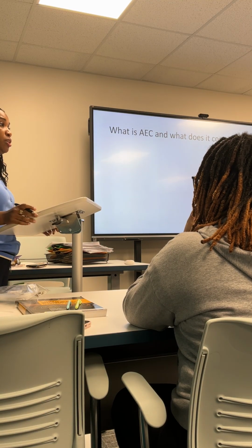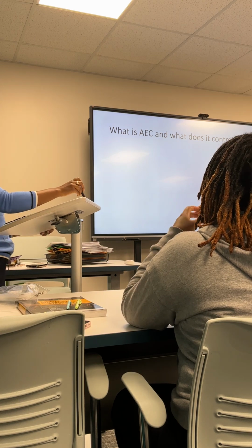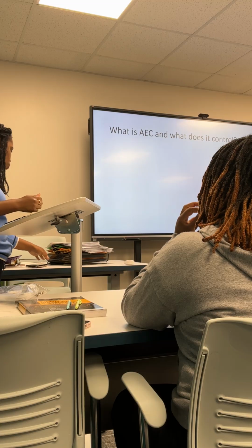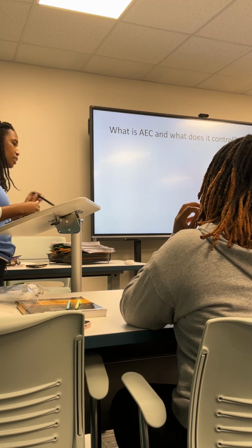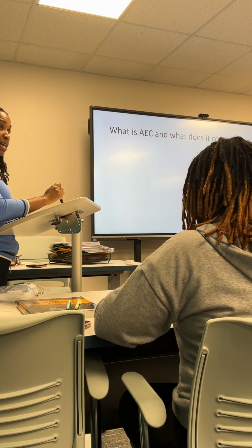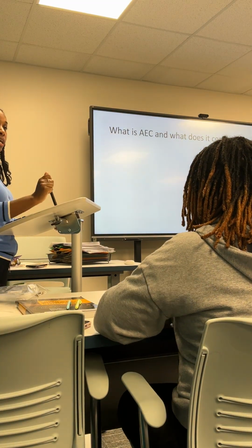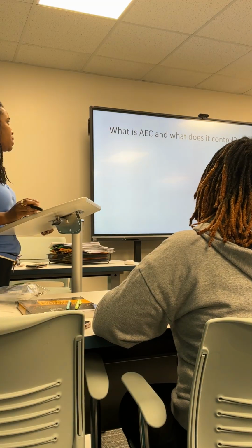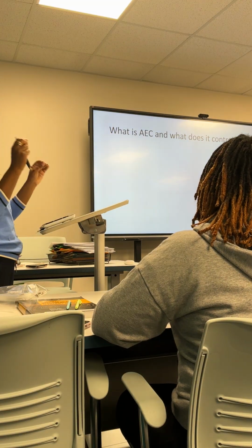Remember all of this is in the console. I don't want to give away questions, but we control KVP, MA, SID. AEC controls time. We can do time manually as well, but AEC controls time. Don't forget it. AEC is a timing mechanism.